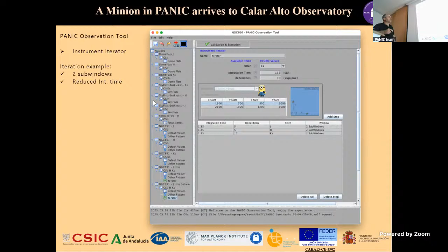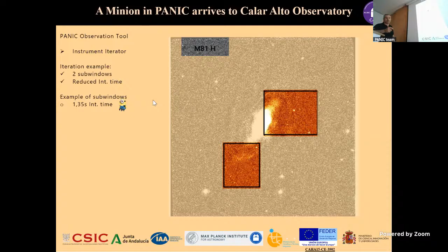And this panel also allows us to specify the sub-windows that Vianak mentioned before. That allows us to reduce the minimum integration time of the single exposure. Here we have an example of 2 sub-windows that looks like this. And with this definition, we have decreased the minimum integration time to less than the minimum exposure time of the detector, less than half of the minimum.